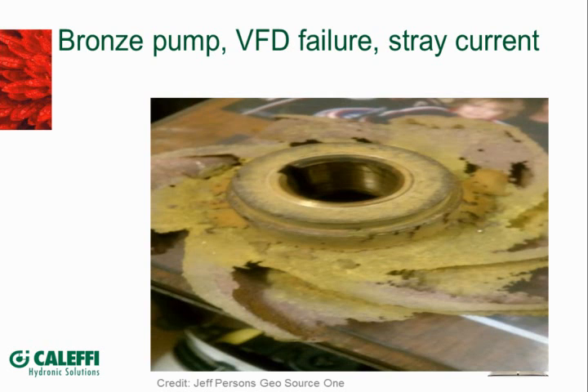Yeah. This is a great slide. It came to me through one of our commercial suppliers, and I was just totally knocked off my feet when I saw it. This bronze or brass pump impeller is 1 year old, and it was on a variable frequency drive motor that had experienced a high voltage surge. They ended up replacing the drive unit on the motor, but did not replace the motor. And my suspicion is that there's been some winding damage in that motor that's causing stray currents to pass through the shaft and dissipate into the fluid that they circulate, because the plumbing system is copper that it's connected to.